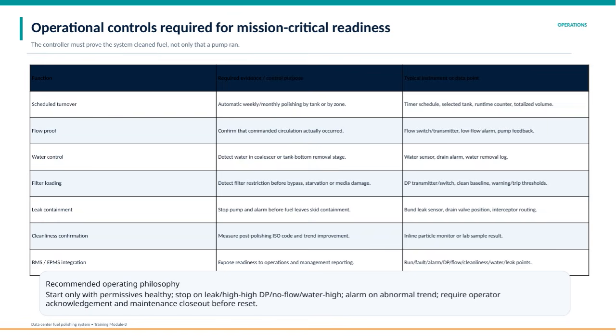As for the recommended operating philosophy, the system should only start when all permissives are healthy. It must stop immediately on conditions like leaks, very high differential pressure, no flow, or high water levels. Alarms are set for any abnormal trends, and operator acknowledgement along with maintenance closeout is required before resetting the system. This approach ensures safe, reliable, and effective operation every time.